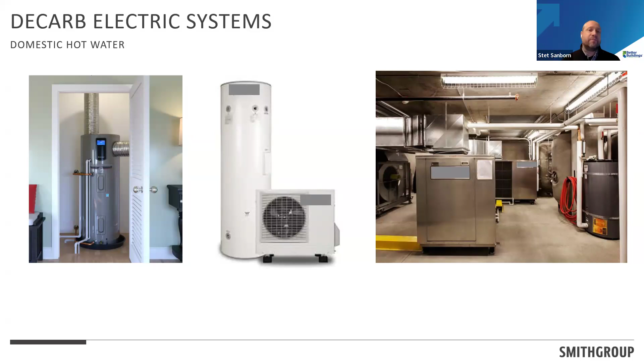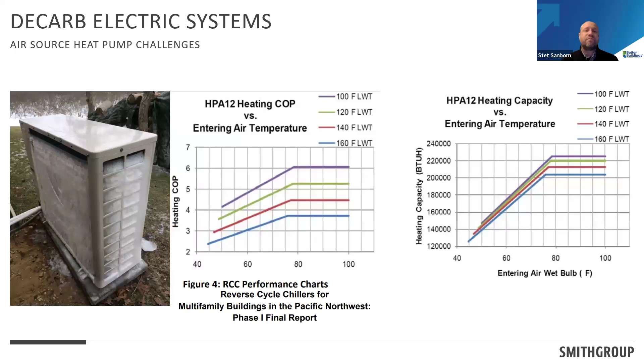Now, one of the things, and I already saw a bunch of questions in the comment section or in the Slido, is: what about cold climate? What happens? That is a totally legitimate question. When air source heat pumps are in cold climates, as your air temperature outside is going down, so is your performance and so is your capacity. Both of those things are going down essentially linearly with outside air temperature. And so it's really, really important that when your design team is selecting a heat pump, they take into account that degraded or derated performance for outside air temperature. However, that's not our only option at hand to overcome some of those performance challenges. Next slide.